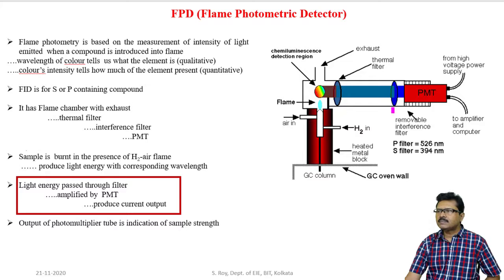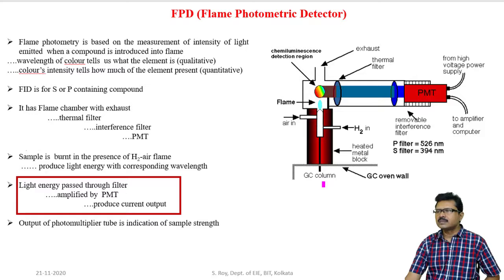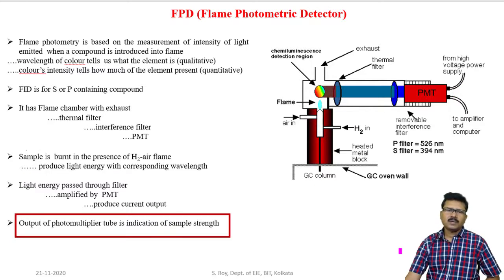If we want to detect sulfur content, the monochromator should be chosen to allow light energy with a wavelength of 394 nanometers. Ultimately, the corresponding light energy passes through the interference filter and is detected by the photomultiplier tube. The photomultiplier tube multiplies the signal and produces an electrical output. The magnitude of this electrical output is the indication of the strength of the sample. If the concentration of sulfur or phosphorus is higher, the output will be higher; if lower, the output will be lower.